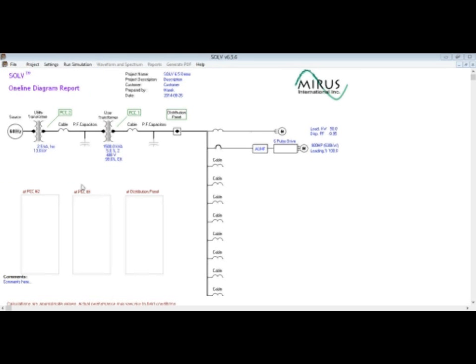To enter cable information, simply click the cable symbol and cable data can be entered. So I selected 300 feet and 2 gauge wire with number of one conductor per phase. When I click OK, this information appears on the single line. If we prefer to be working in metric cable sizes instead of imperial, this can be changed in settings and changing the setup to metric. You can see that cable size changed to millimeters square and length to meters.